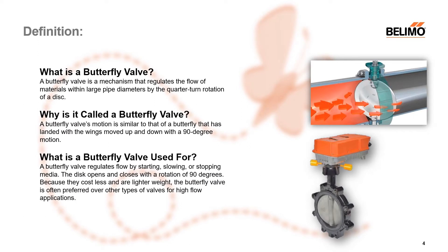By definition, a Butterfly Valve is a valve with a mechanism that regulates flow of materials within large pipe diameters by the quarter turn rotation of a disc. You can see in the picture on the far right, media coming along in a large pipe hits the disc and can go on either side and pass through. They call it a Butterfly Valve because its shape somewhat mimics the motion of a butterfly, where the wings move up and down in a 90-degree rotation. Traditionally they're used to regulate, stop, or slow the media on large-scale pipes — large flow, large pipes, large valves. They're usually a little bit smaller and less expensive compared to other high-flow valves in the marketplace.